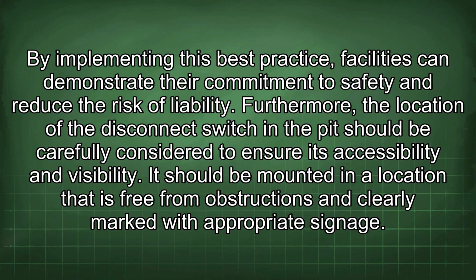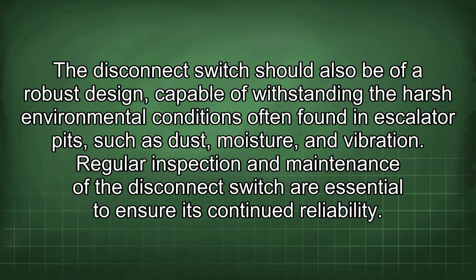Furthermore, the location of the disconnect switch in the pit should be carefully considered to ensure its accessibility and visibility. It should be mounted in a location that is free from obstructions and clearly marked with appropriate signage. The disconnect switch should also be of a robust design, capable of withstanding the harsh environmental conditions often found in escalator pits such as dust, moisture, and vibration.